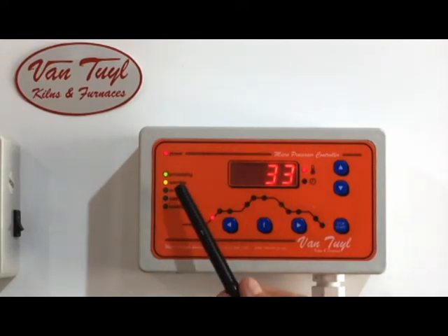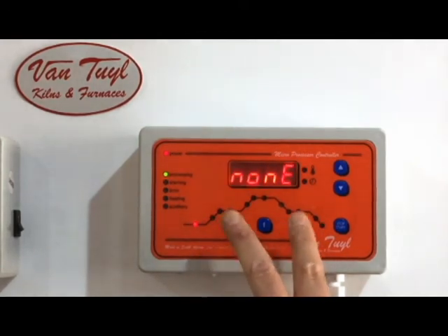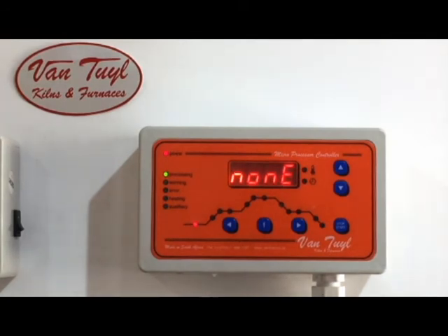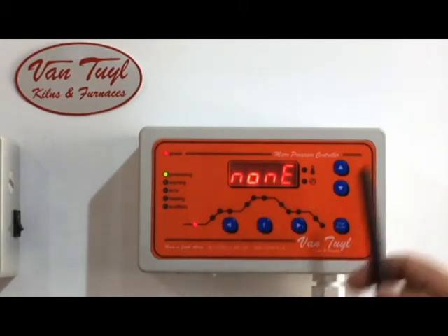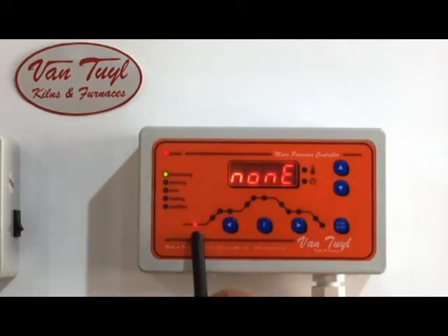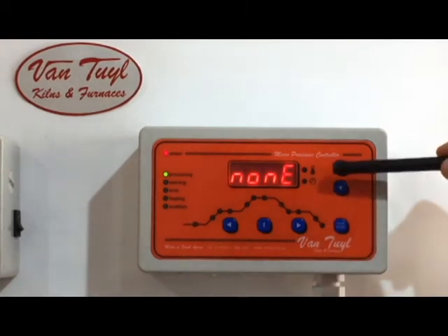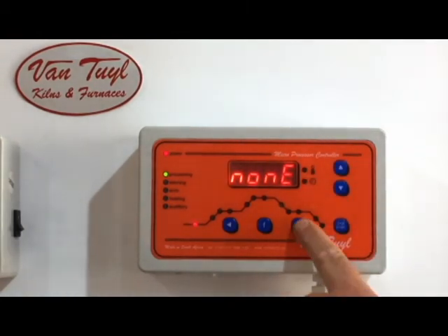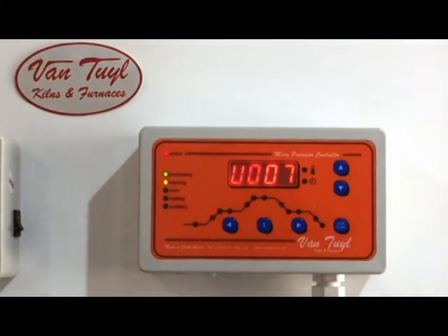But at the same time, you will see the warning light, because it is warning you that something has happened during the course of your program. Now, to determine what that particular error or warning is, you will press both your left arrow key and your right arrow key at the same time. This will take you into your diagnostic screen and also highlight your steps along your graph. So as you can see here on your first step, which is the delay, it indicates that there is no error. We will then use our right arrow key to move to the next step.